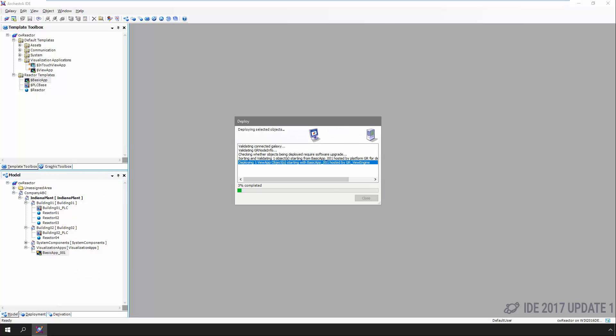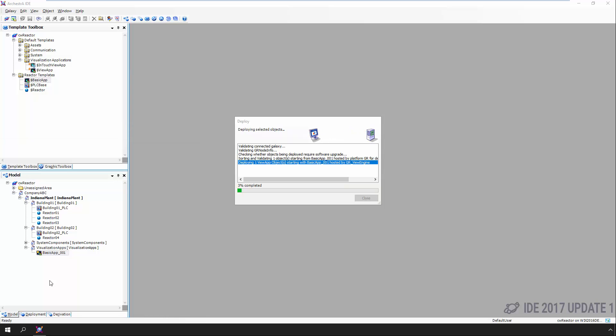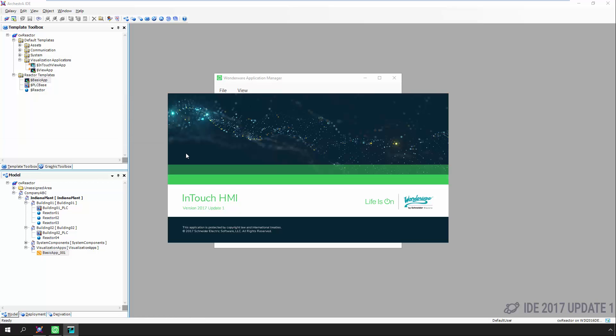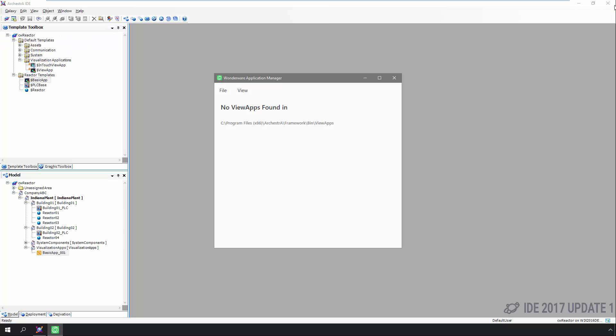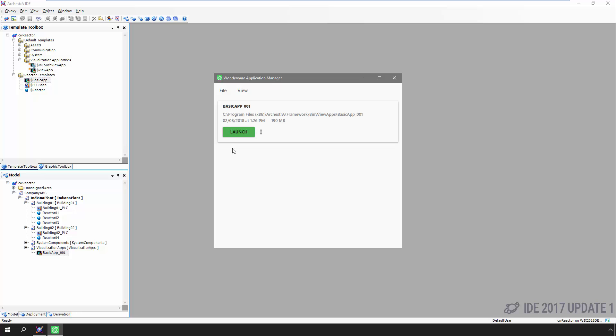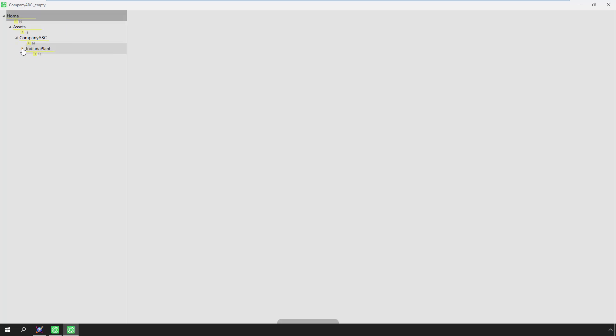We access InTouch OMI applications through a new Wonderware Application Manager. Some of you may be wondering why you don't just use the InTouch Application Manager — the answer is that you could only run one traditional InTouch HMI application at a time using the InTouch Application Manager. InTouch OMI actually allows us to run multiple InTouch OMI applications simultaneously, so a new application manager was needed to provide this capability. Within the Wonderware Application Manager, we now see our application. We launch it, and we can see the screen profile enables everything to fit just like we laid it out, without any problems.